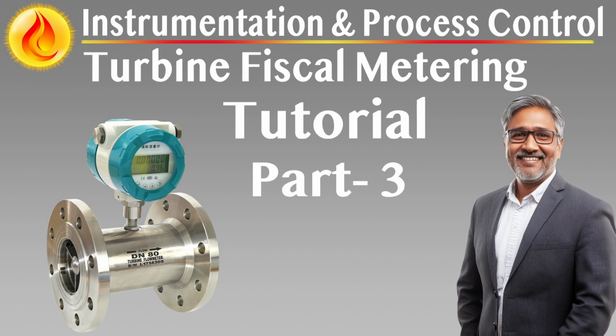Mechanical construction and maintenance accessibility. Turbine meters must be designed for long service life in continuous flow applications, with rotors, bearings, and internal components selected for durability under the fluid's chemical and thermal properties. Meters must include provisions for inline removal and reinstallation without disturbing adjacent piping. Flanges and body connections must support safe removal and resealing. All wetted materials must be chemically compatible with the process fluid and rated for the maximum pressure and temperature expected in the line. Meters must include provisions for identifying rotational drag or obstruction, such as vane failure detection systems or rotor speed diagnostics.